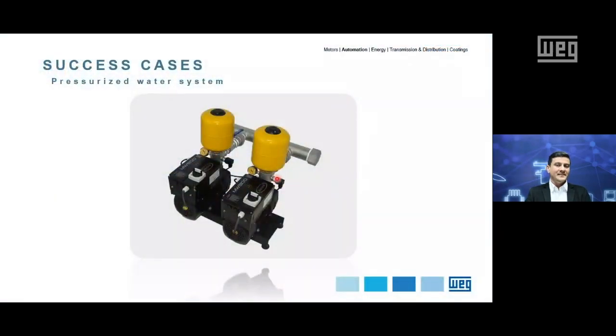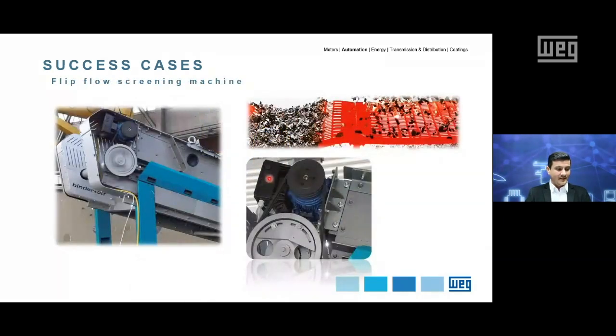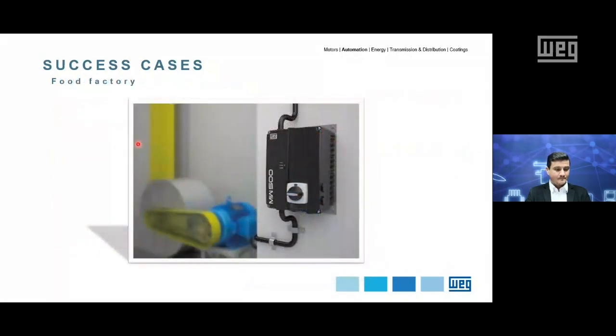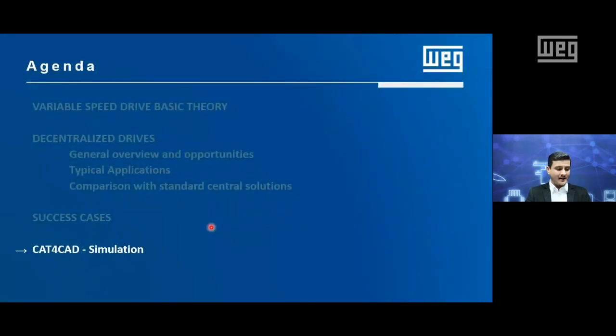Here we have an IP66 inverter assembled directly on motor terminals. This is for a pressurized water system. This is a WEG drive system for the flip flow screening machine. As you can see here, the VSD motor has been placed in the machine structure for this application. In a food factory as well, we have a decentralized drive IP66 installed against the wall, but close to the motor as well. Just a few examples to show you the possibility of using a decentralized drive.